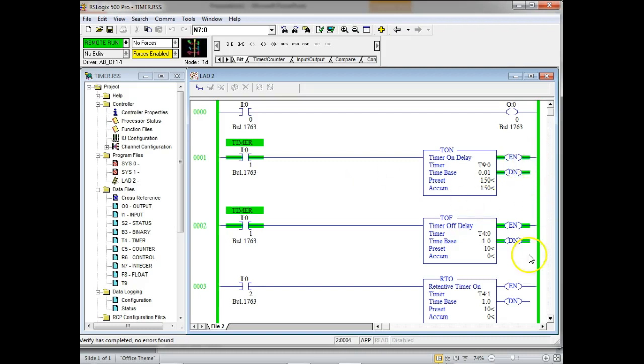We got a timer done. This one says it's done already, right? Yep. So this is switch 1. So let's close switch 1. Timer 1 resets to 0, and then timer 2, the off delay, comes up and does what? Now here the done bit is opposite of what we expected it to do. Right? So here, with the off delay, the done bit goes false when the timer times out.